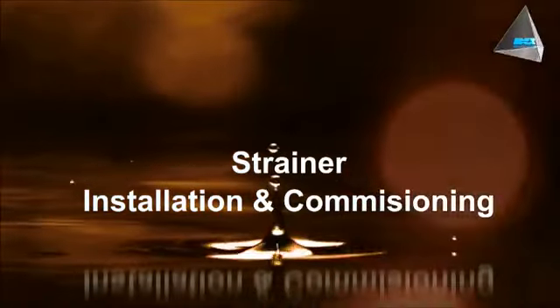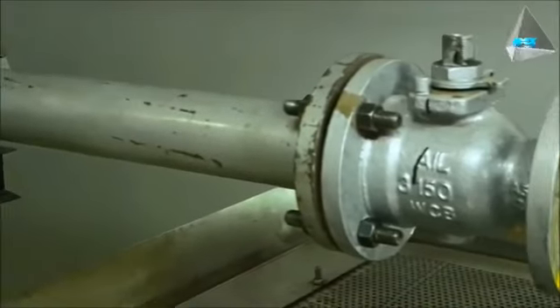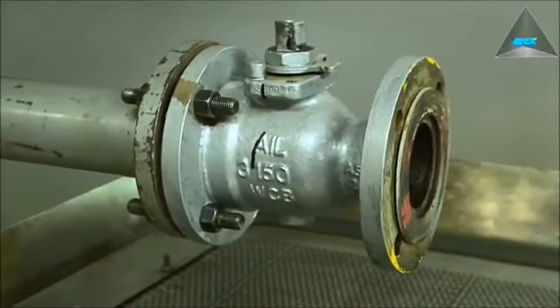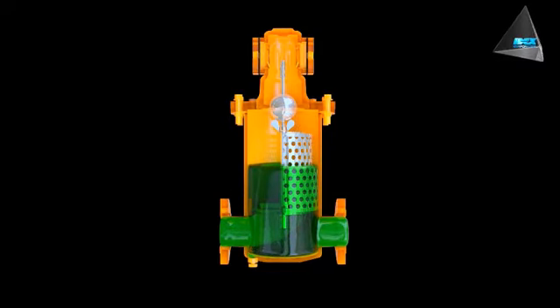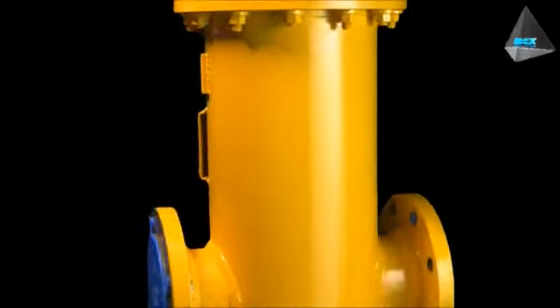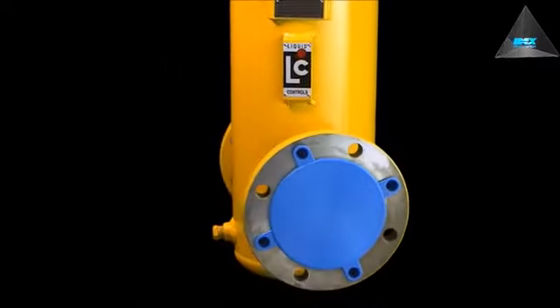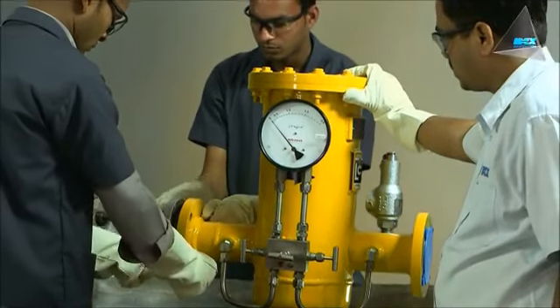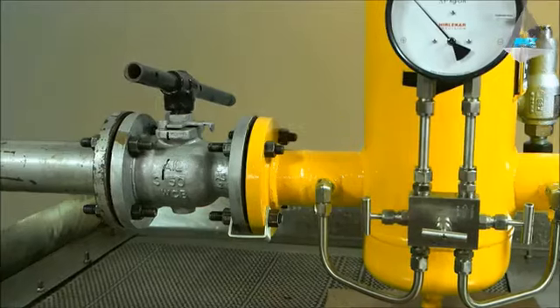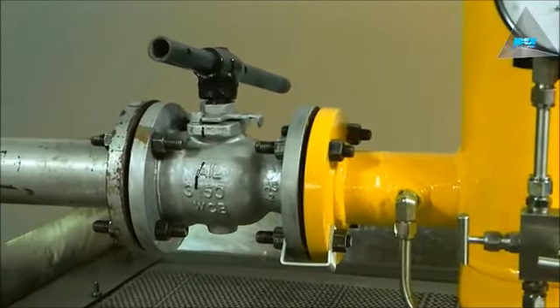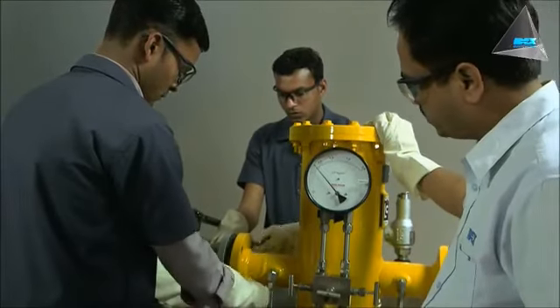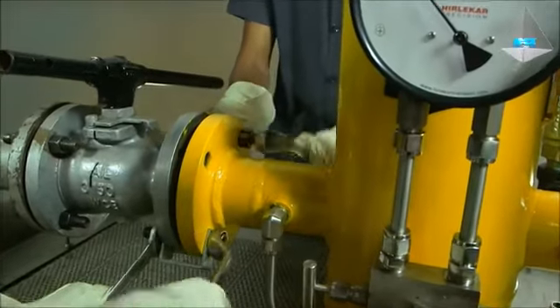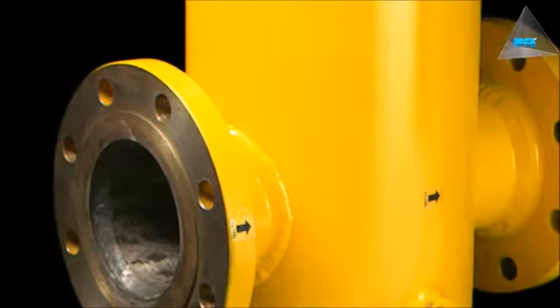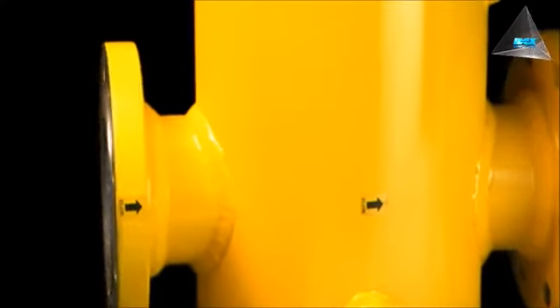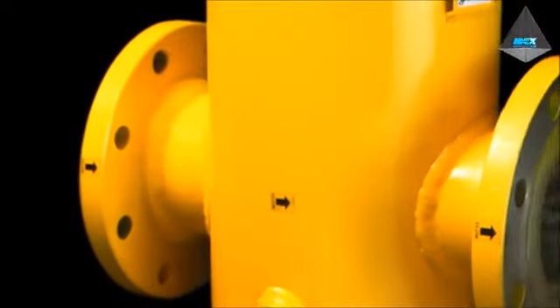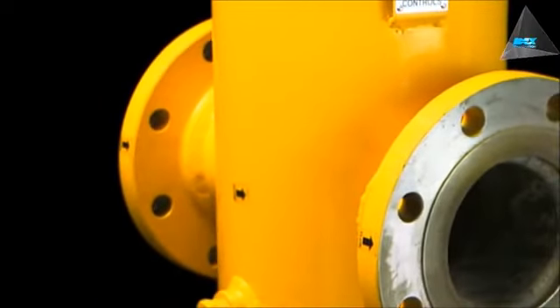Strainer installation and commissioning. The entire piping system should be thoroughly flushed of all debris prior to installing the strainer. The system should be designed to keep the strainer full of liquid at all times. Protective caps placed in the openings of the strainer before shipment should remain in place until you are ready to connect the piping. The strainer installation position should allow easy access for service. Provide an isolation valve at the inlet of the strainer for servicing and cleaning of the basket. Never hang a strainer on the connecting piping. When piping the strainer, do not create pipe stress or strain in order to complete the installation. The direction of installation with respect to the flow, left to right or right to left, should be maintained for the FS series. Look for the arrow marking for proper flow direction.